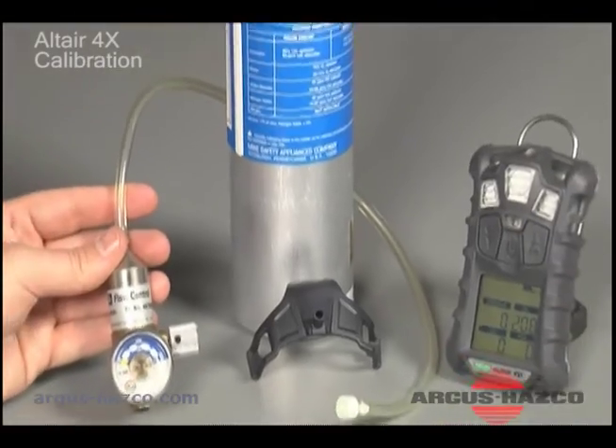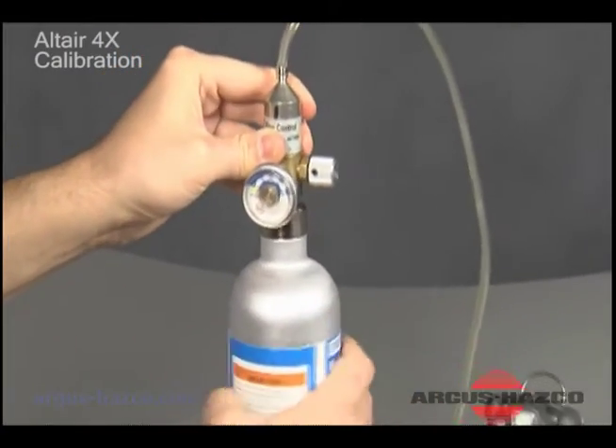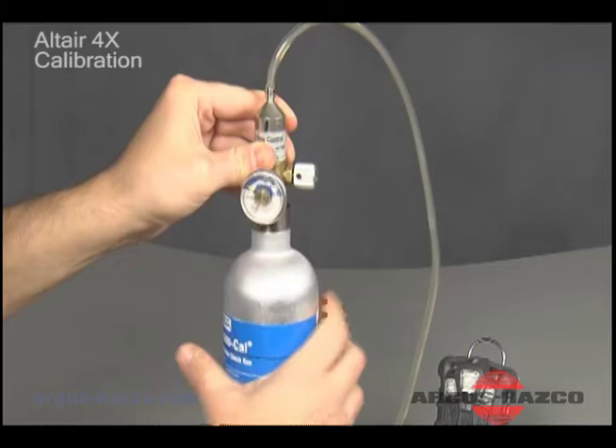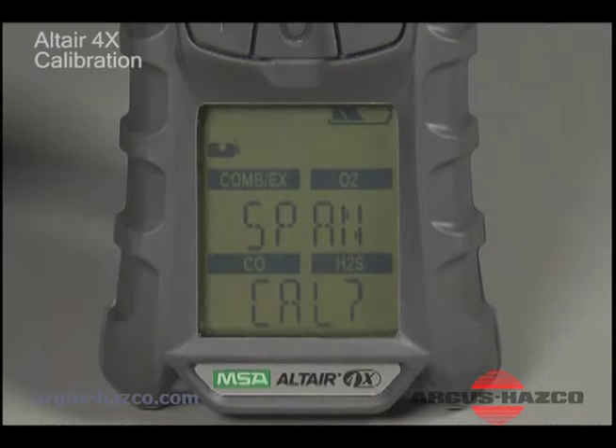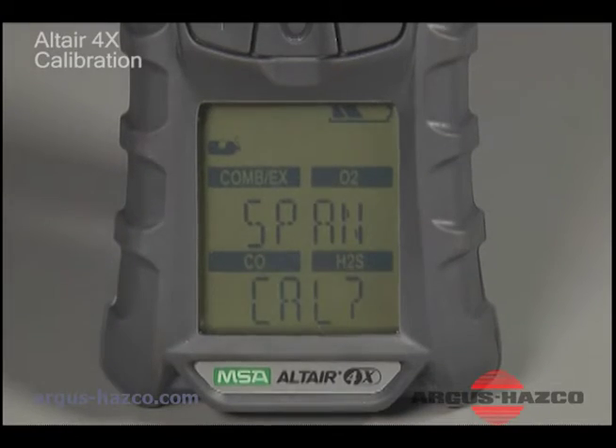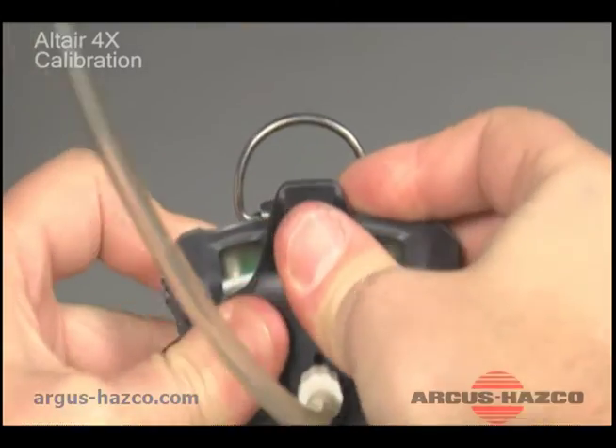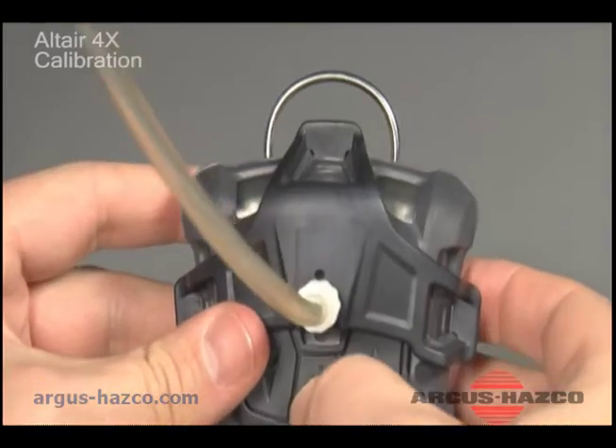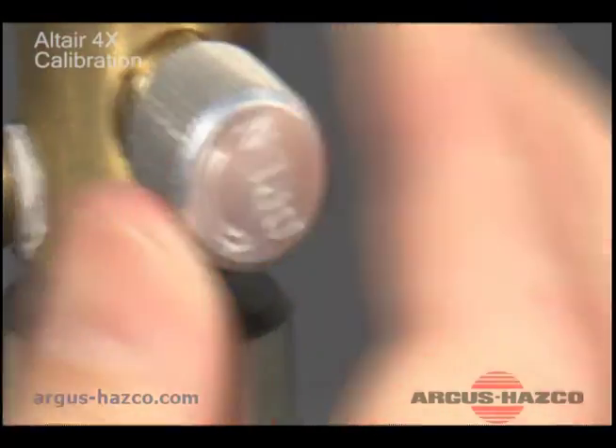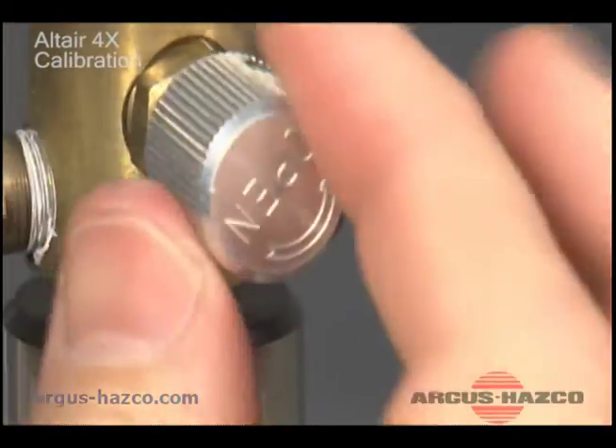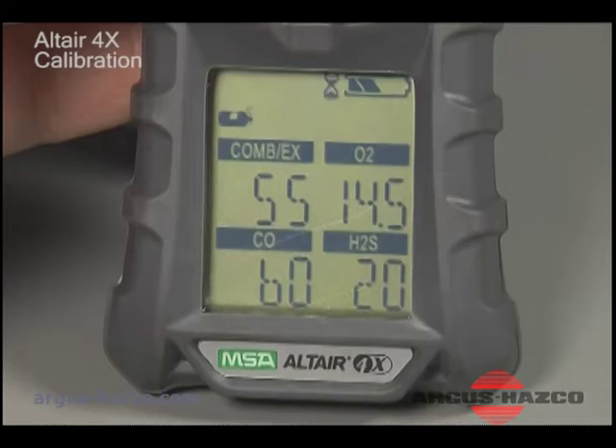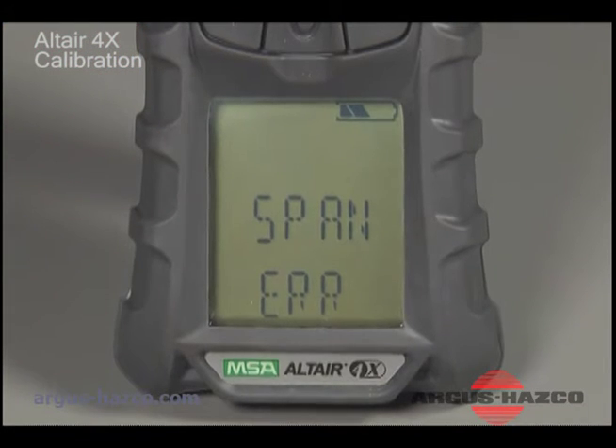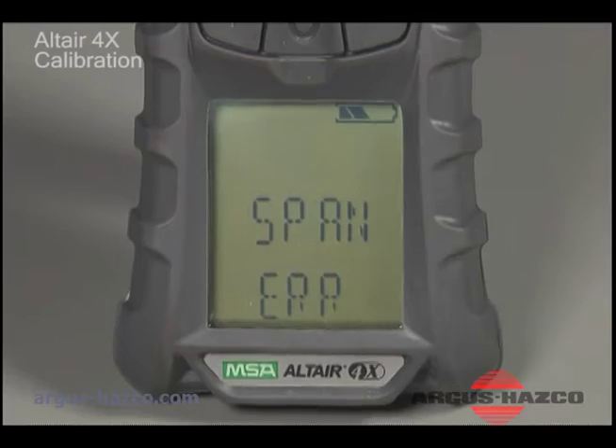supplied with the instrument. Have the regulator connected to the cylinder and the tubing connecting the regulator to the calibration cap. As span cal displays, quickly connect the calibration cap to the instrument, press the Accept button, and open the regulator valve to start calibration. Successful span calibration is indicated by the message Span Pass. An unsuccessful span calibration will be indicated by Span Error.